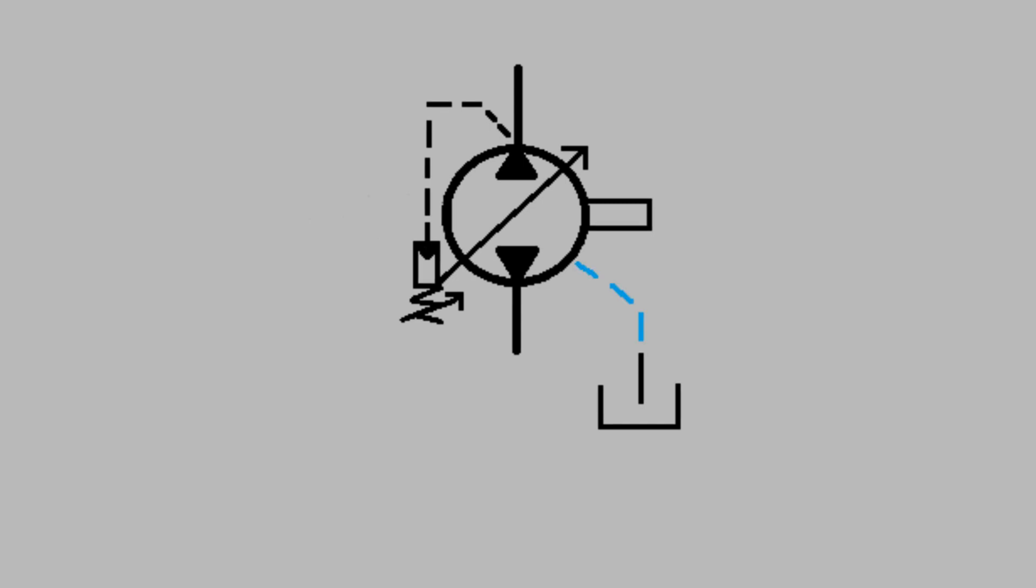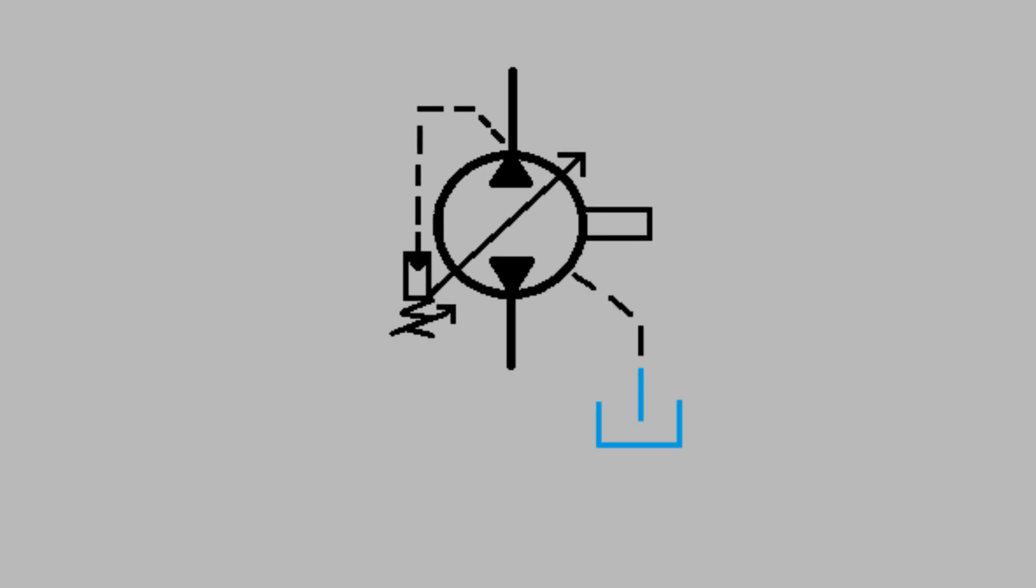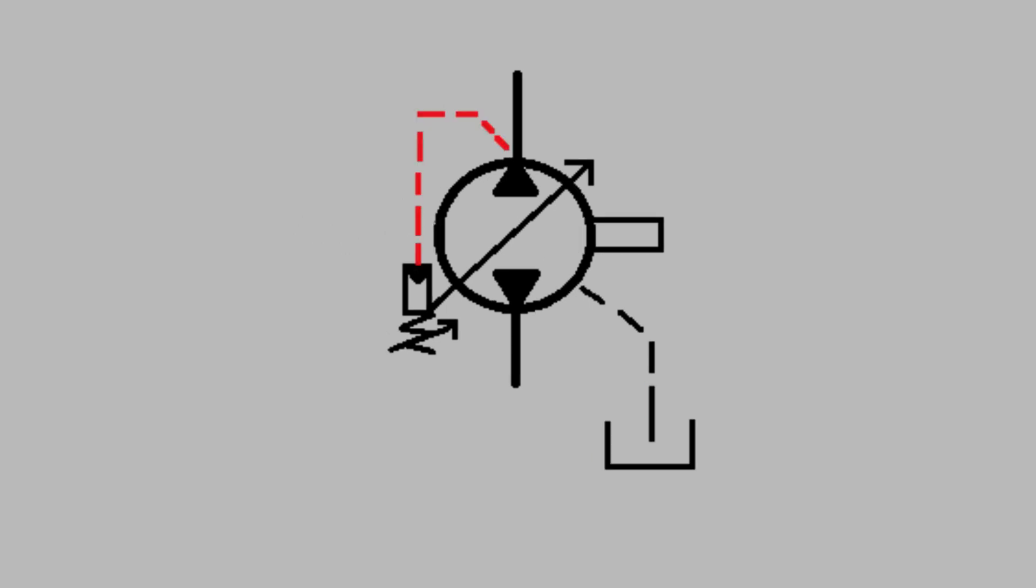There may also be a dashed line that indicates either a case drain or pilot line. The quick way to decipher a case drain line is by looking where it goes. If it runs straight from your pump or motor to your tank it is a case drain. By the way this little symbol means reservoir or tank. However if it runs back to the pump or to a valve it is a pilot line.